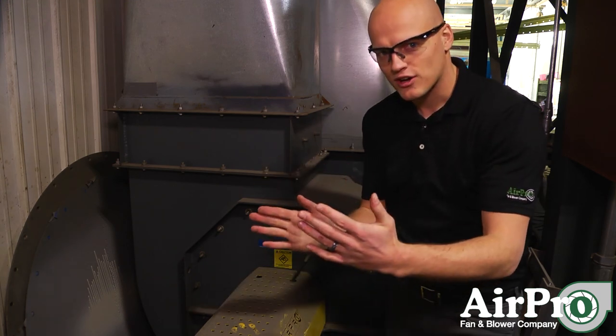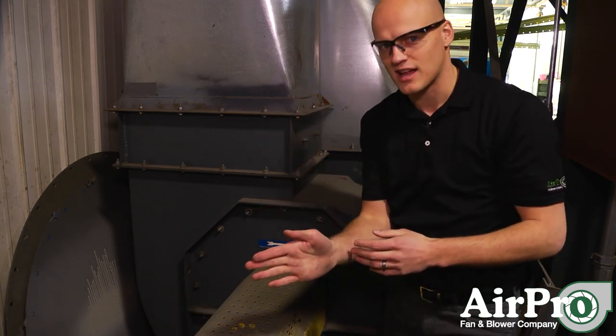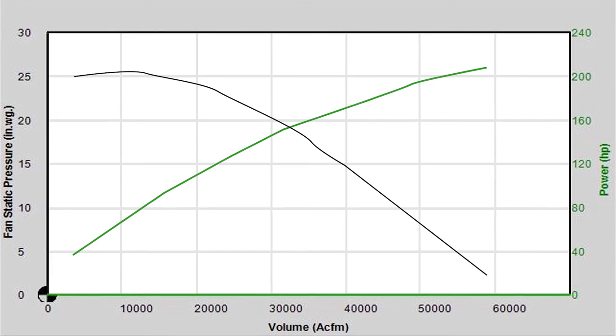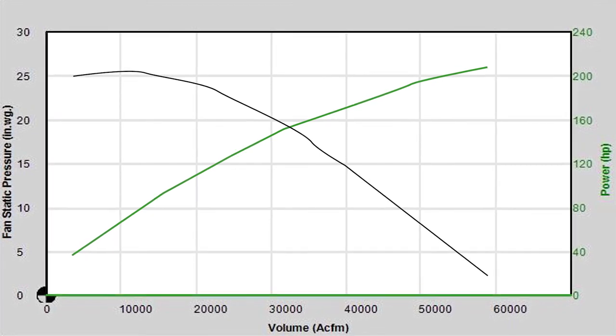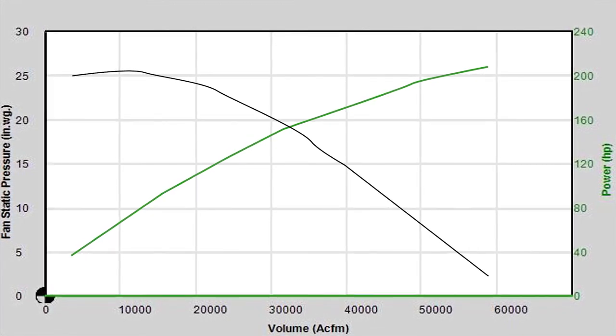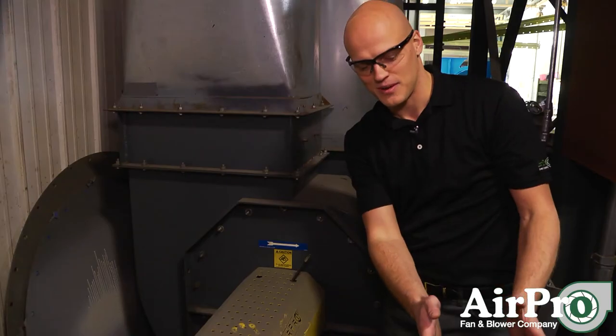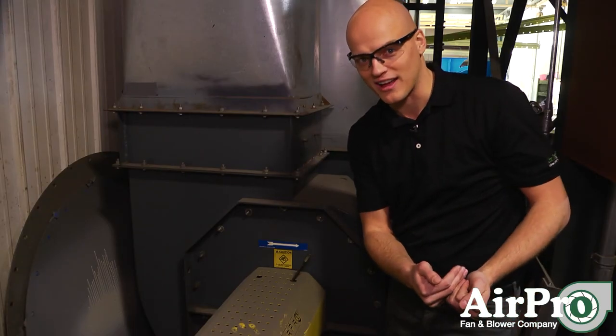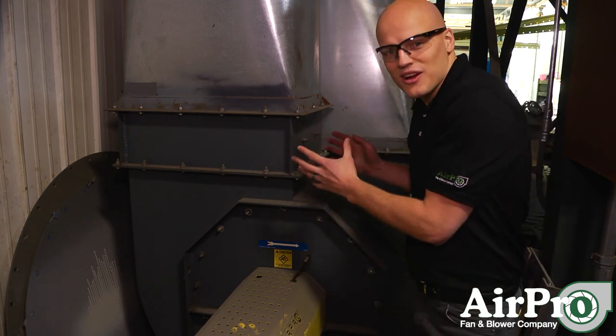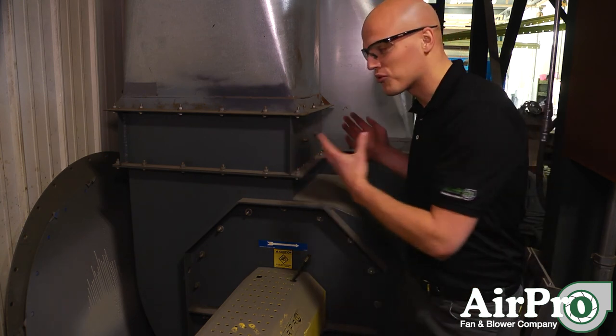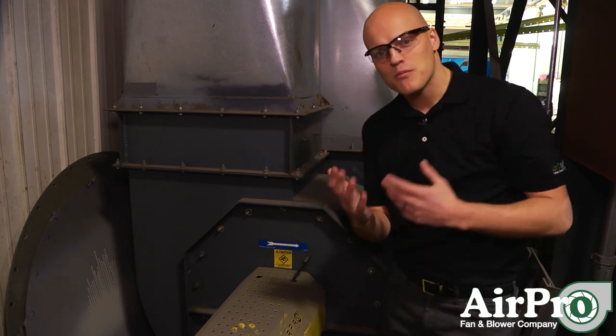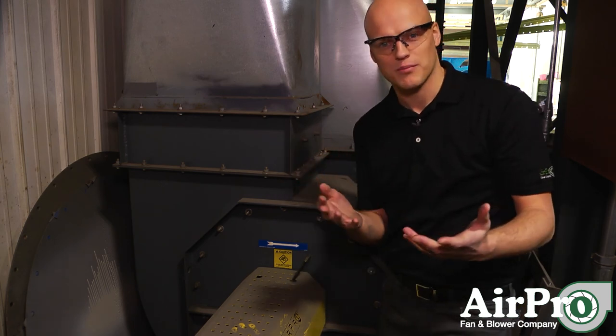Now go back to your fan curve and look at 25 inches of static pressure. Does it make more sense now? Going down from that point, you're probably intersecting the horsepower curve very close to 100 horsepower, which aligns with what you read from the amp measurement off your motor legs. That's how you troubleshoot a real fan application. This is just one example — there are many more things that could affect your static pressure readout.